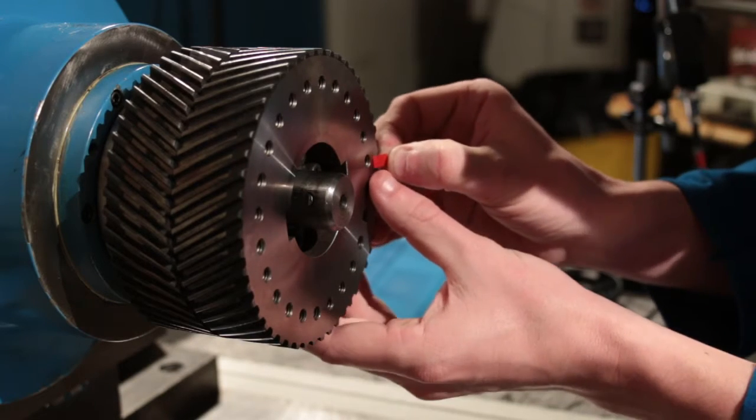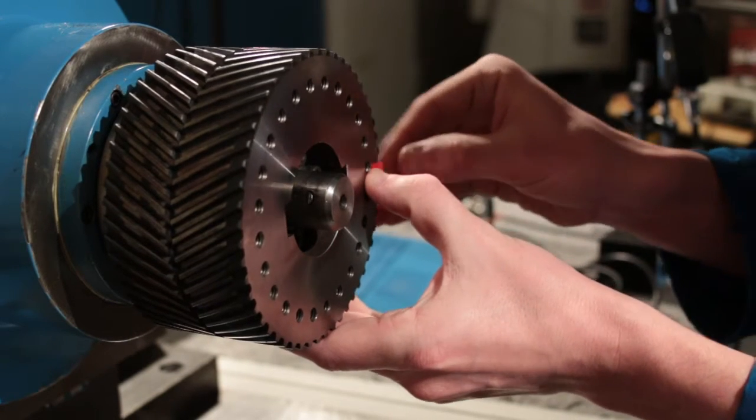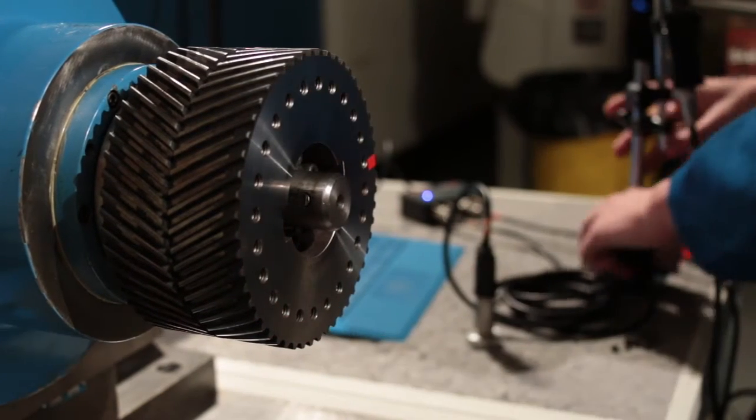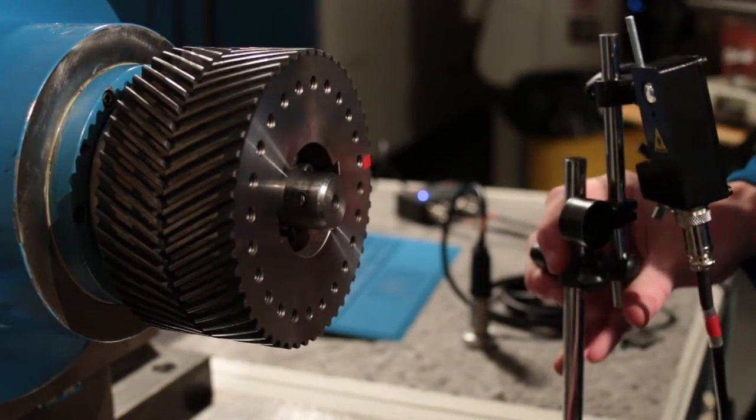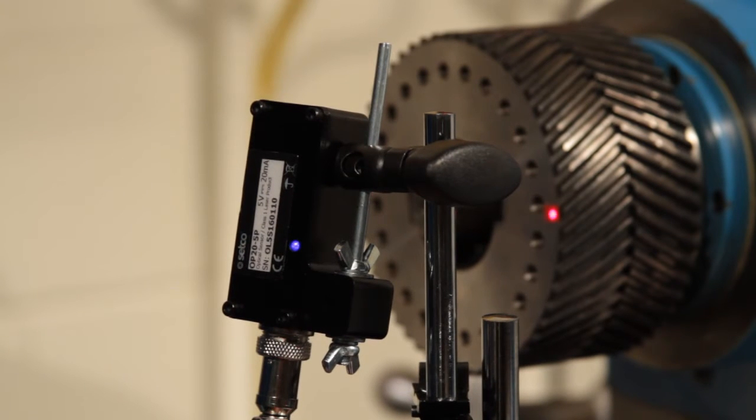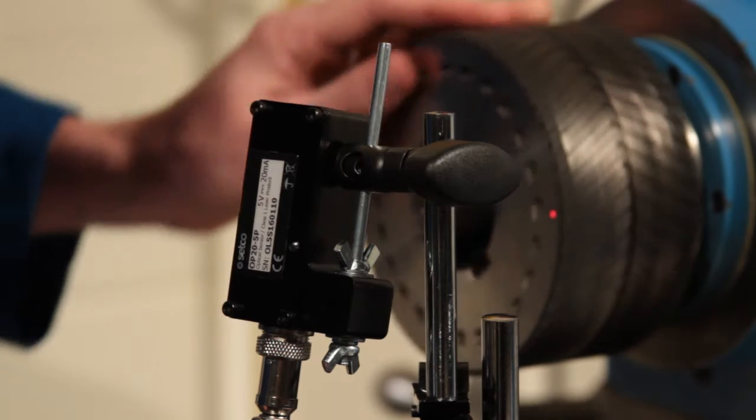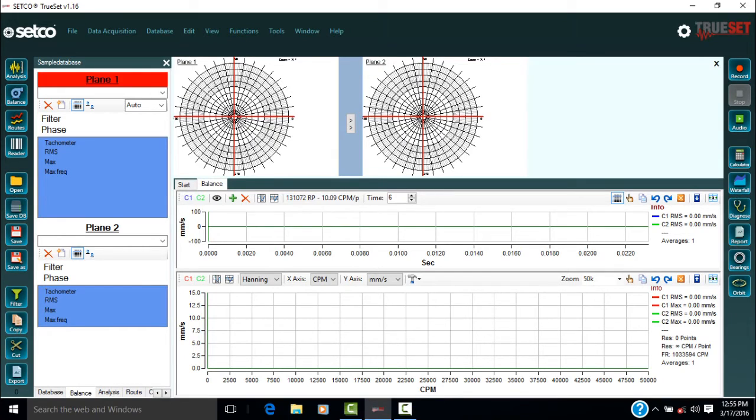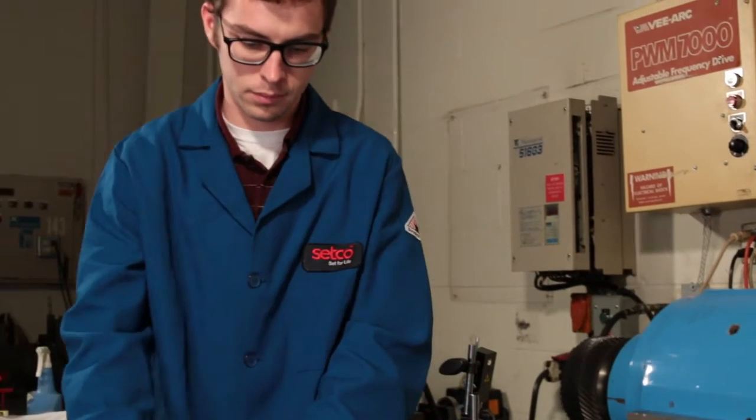With the equipment powered off, place the TAC tape on the rotating shaft, preferably in line with a balance hole. The tachometer should be placed with the laser hitting the tape. The blue light should light up only when the tachometer is pointed at the tape and in proper position. The angular position of the shaft where the TAC laser hits the leading edge of the tachometer tape sets the zero position for making angular measurements, which match the polar graph on the screen.